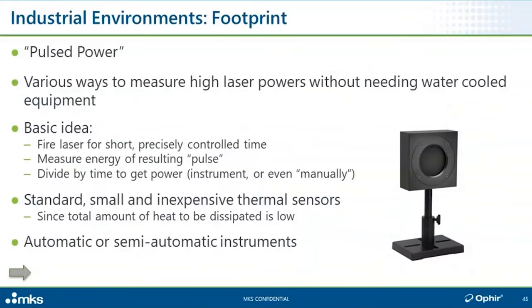Industrial environments. So we'll begin with the footprint issue. There are various ways to measure high laser powers without needing a very massive water-cooled sensor. The basic idea is that we want to limit the exposure time to the high power to as short a time as possible. So the trick that we use in some of our sensors and some of our instruments is what we call pulsed power mode.